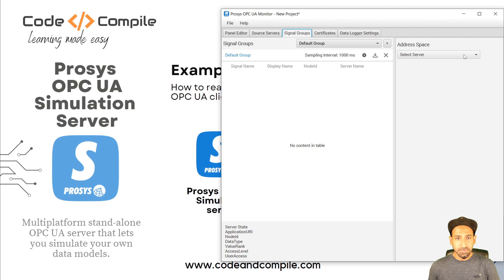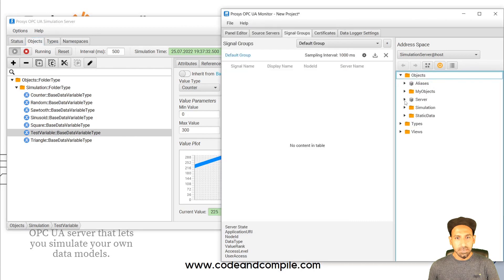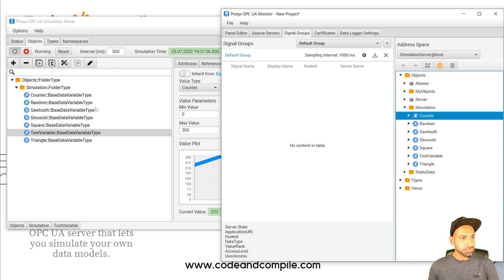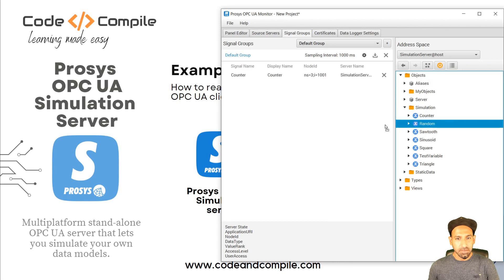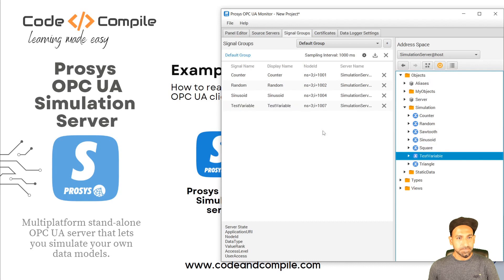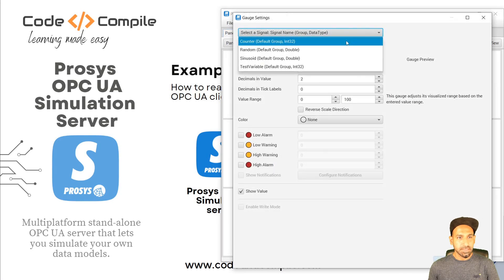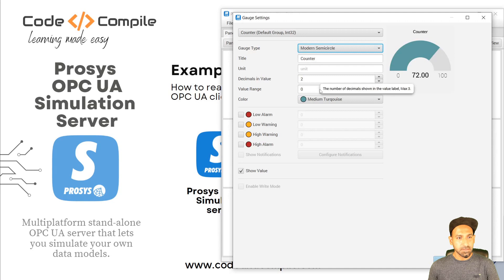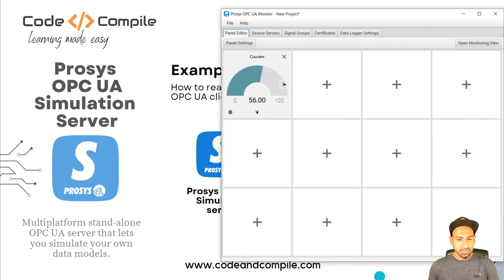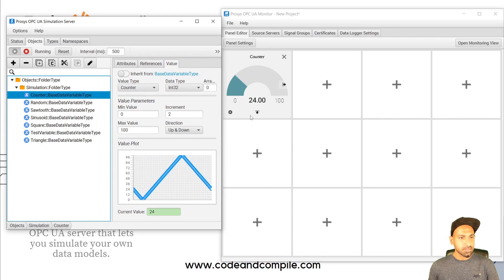Now go to Signal Group and define your server. As we saw in the simulation server, we have a Simulation folder inside Objects. Go to Objects, find Simulation, and you'll see the Counter and all defined variables including the test variable. Drag and drop the counter, random, sinusoidal waveform, and test variable into the group. Then go to Panel Editor, click plus, select a variable like Counter, choose a gauge — for example Modern Semicircle — and click OK. The counter gauge now reads the value from your simulation server in real time.